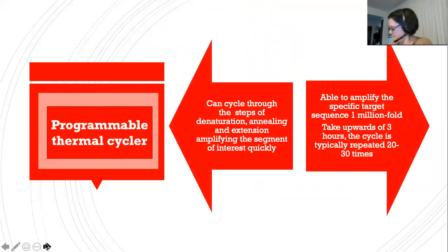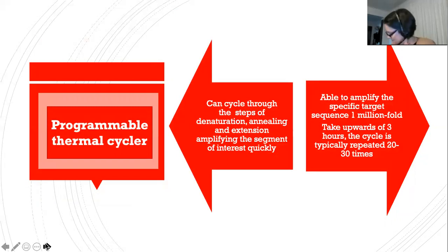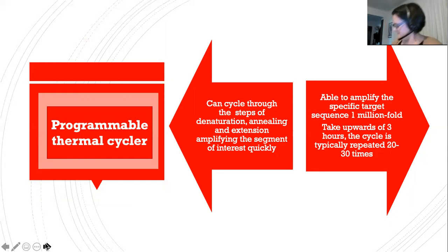An automated programmable thermal cycler is a laboratory machine that can cycle through the steps of denaturation, annealing and extension efficiently, amplifying the segment of interest quickly. A reaction that cycles 20 times will amplify the specific target sequence one million fold and can take upwards of three hours. The cycle is typically repeated 20 to 30 times, and the programmable thermocycler makes this process less labour intensive.